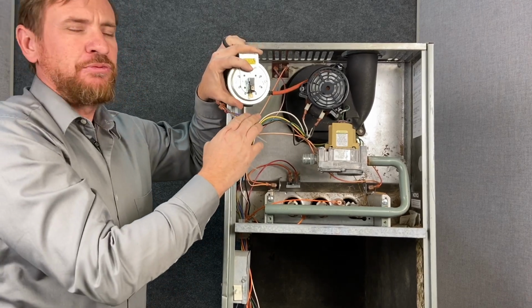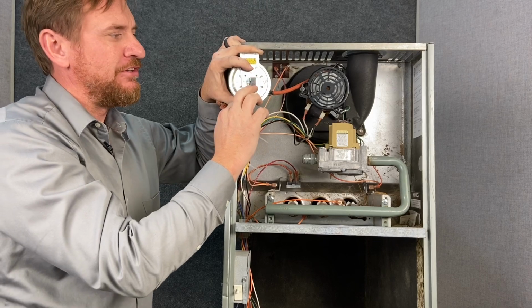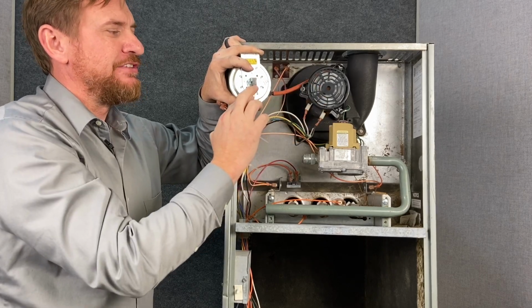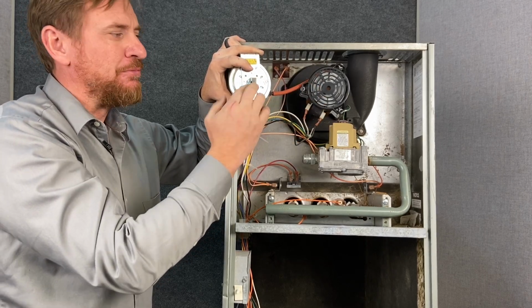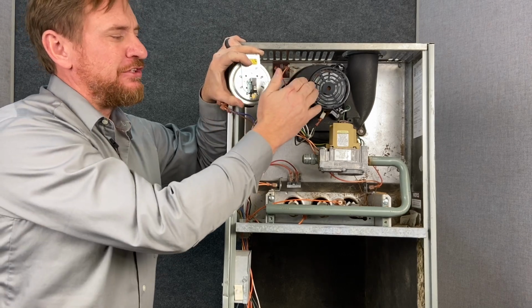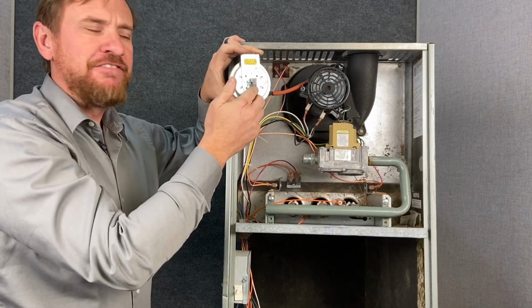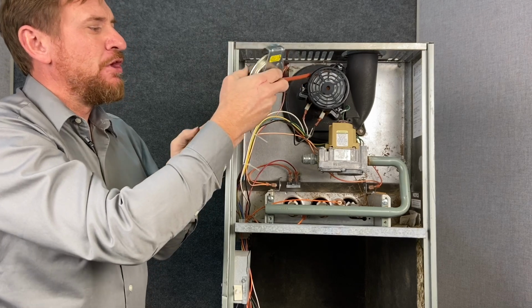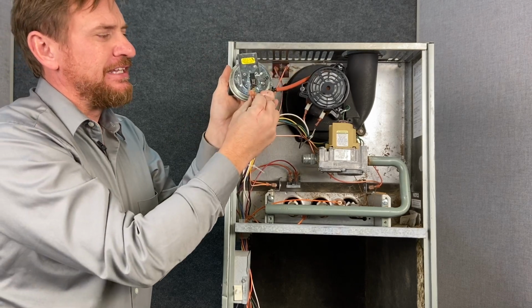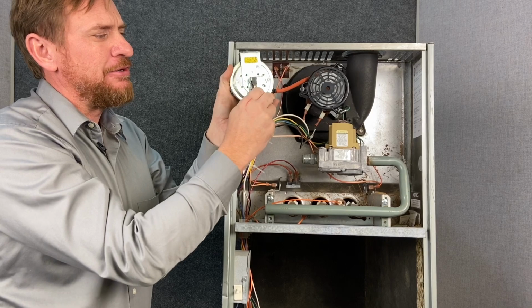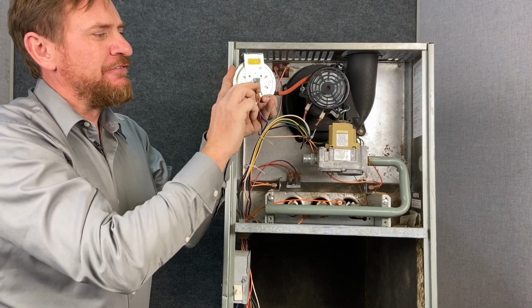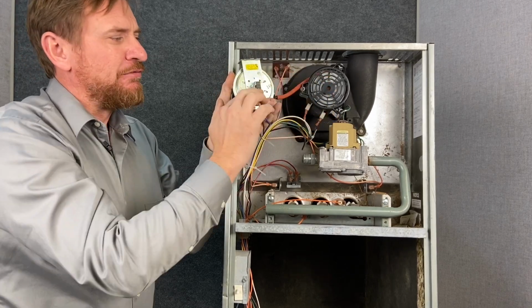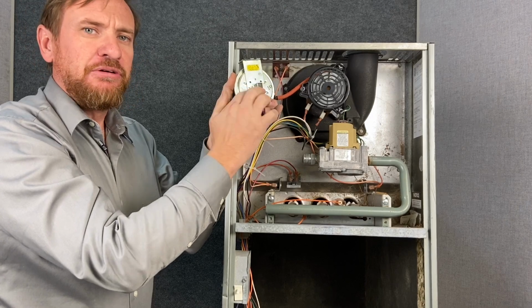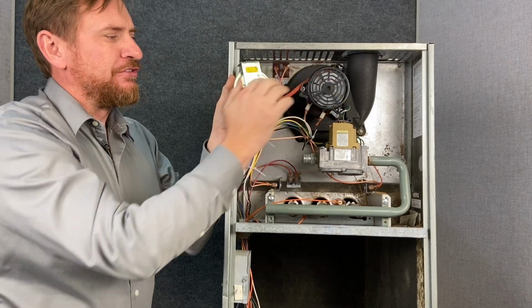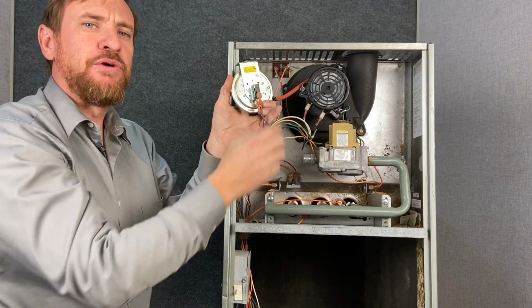And we could actually check this with our meter, setting it to ohms. We can set it to ohms, run our fan motor, and we should see in ohms, this would be 0 ohms. The switch would be closed, and when we shut this motor off, it would show OL, or infinite resistance. The switch is open. We could also check this with voltage. We could leave these wires connected, just pull them down a little bit, and if we check voltage across here, with this fan running, the voltage should go to 0. It's a closed switch. When this fan motor stops, the voltage should show usually 24 volts.